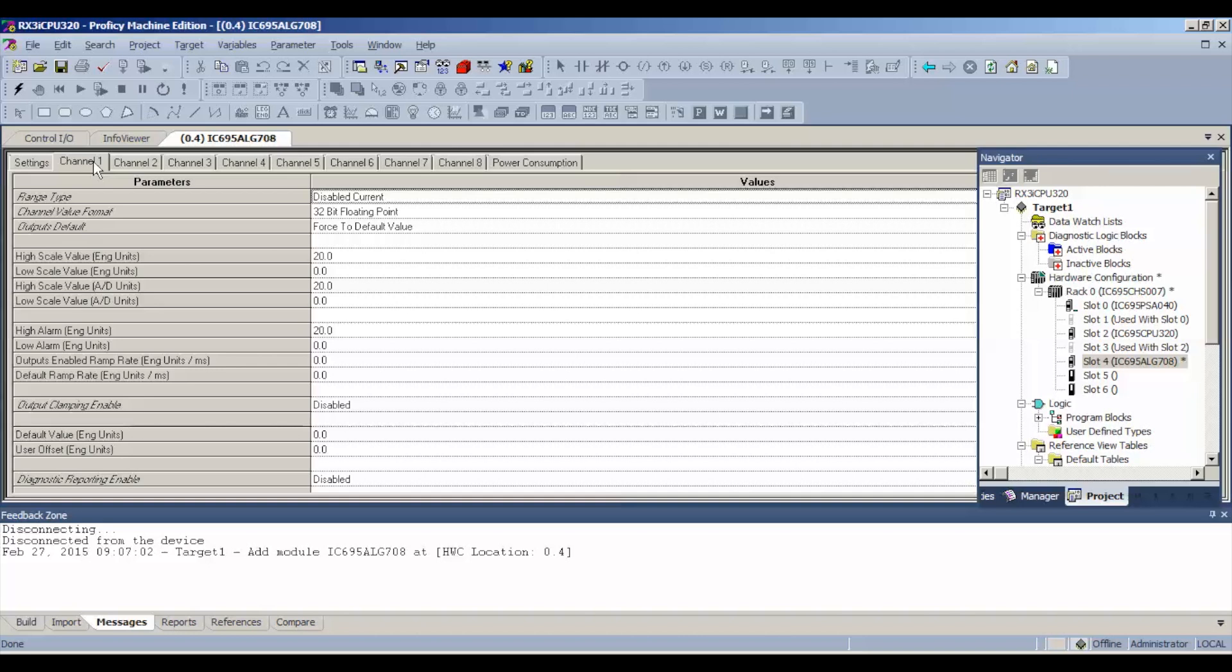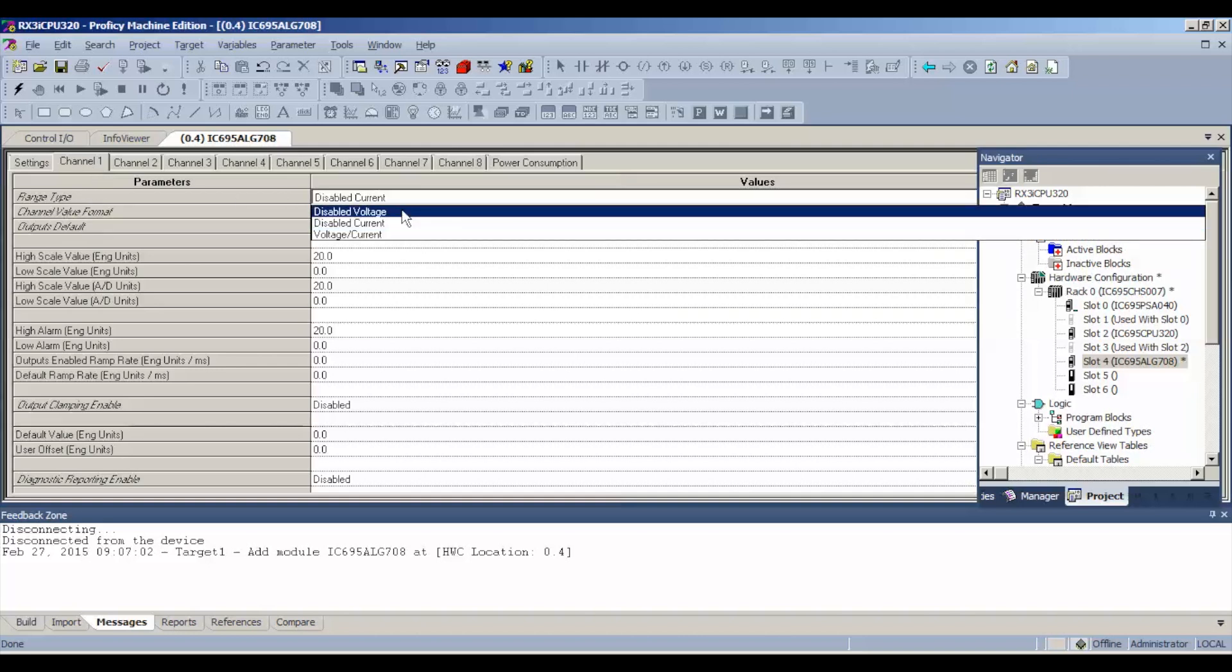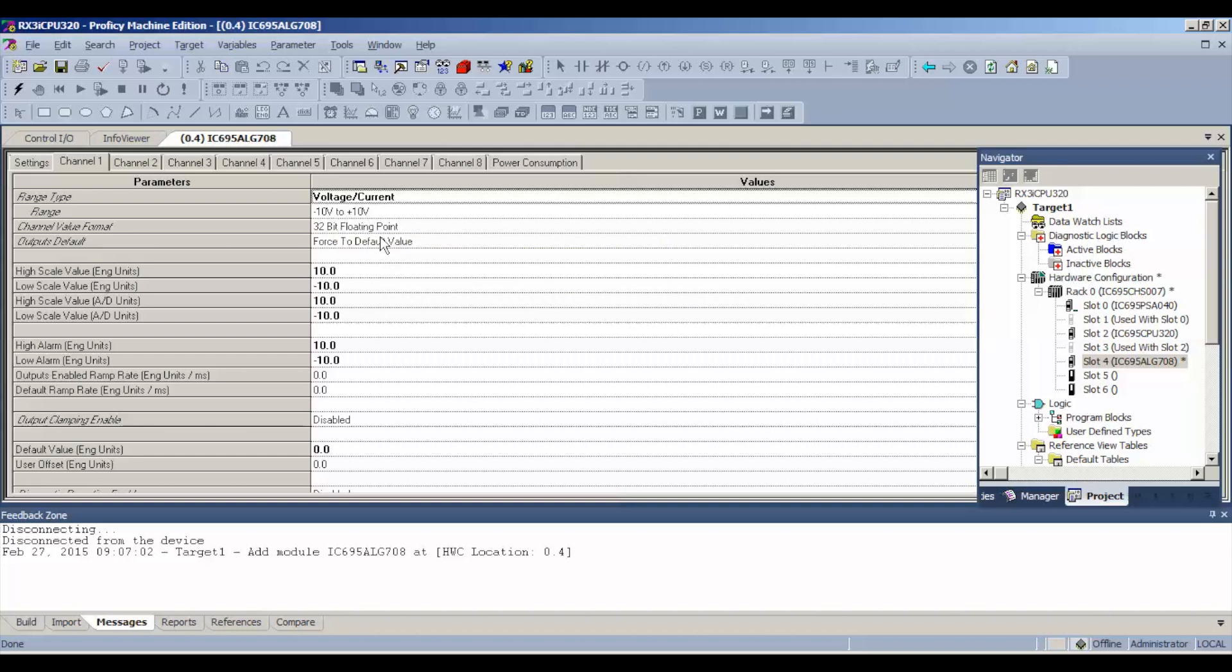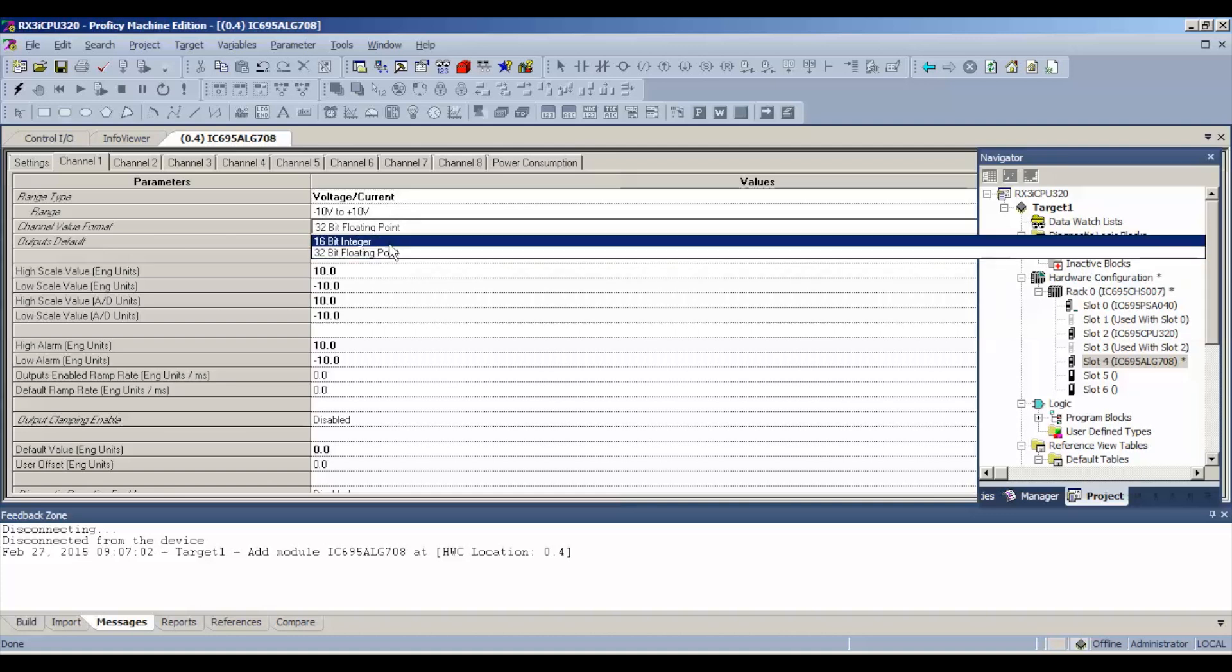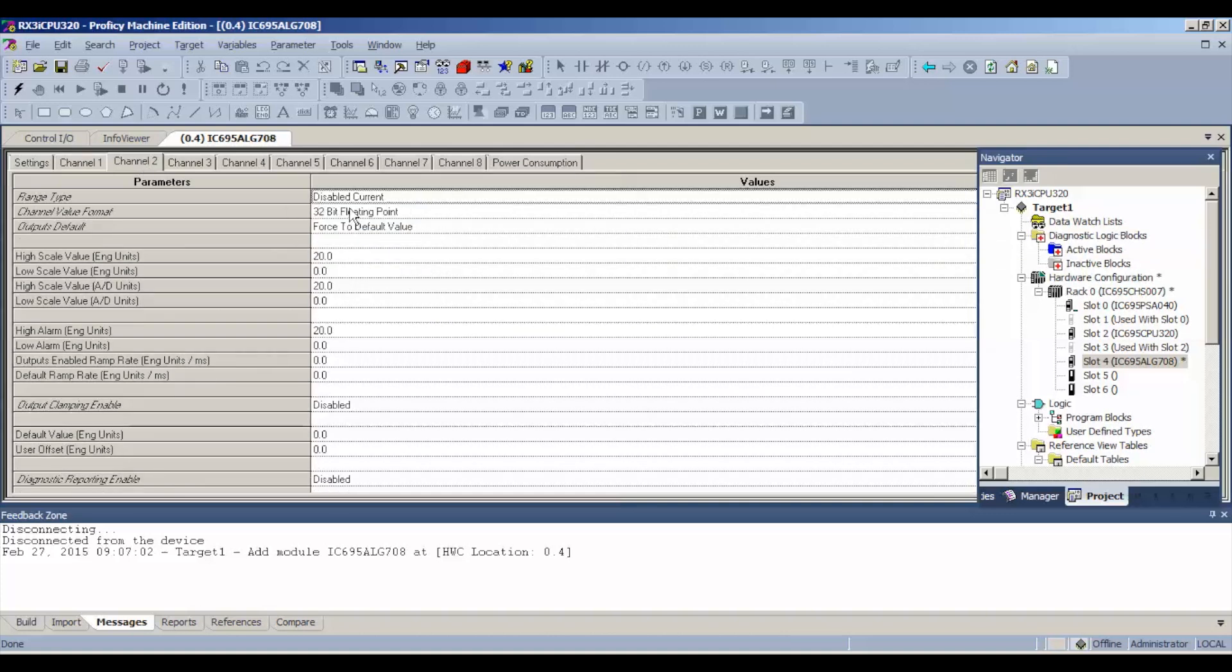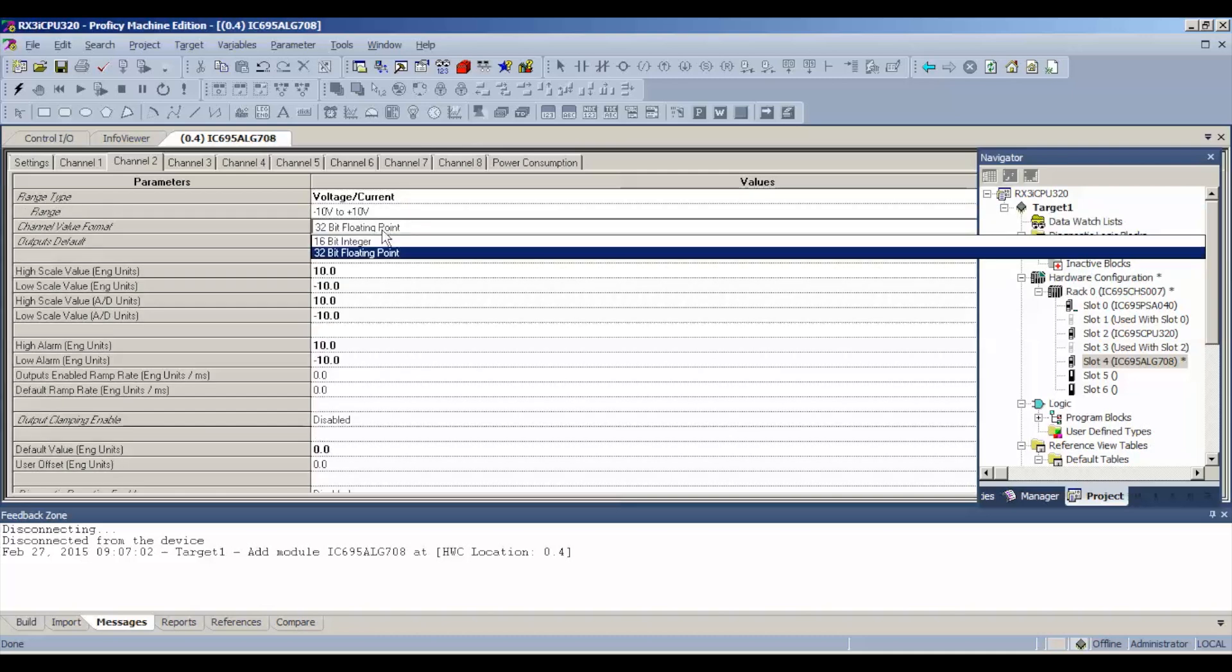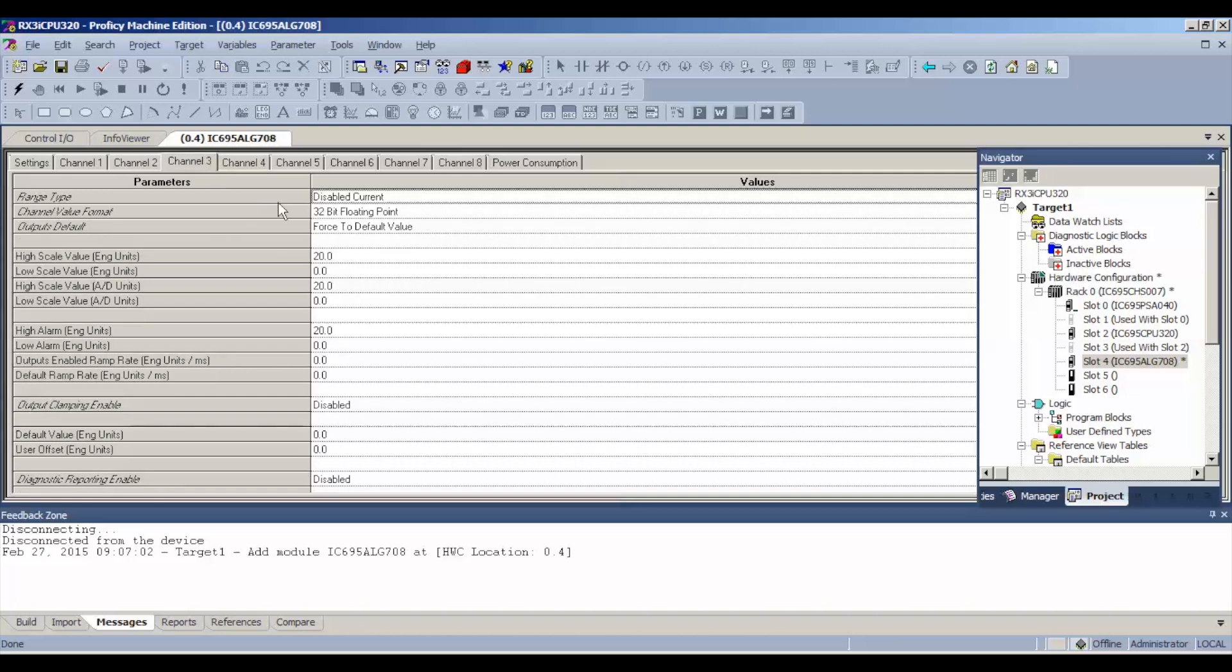The first thing that we want to do is range type. We're going to do voltage, voltage or current is what you want to choose. The first selection is negative 10 to positive 10 volts. We will want to test the voltage first and we're going to do 16 bit integer. Make sure that you do that on each one, voltage, voltage DC is fine, 16 bit integer.